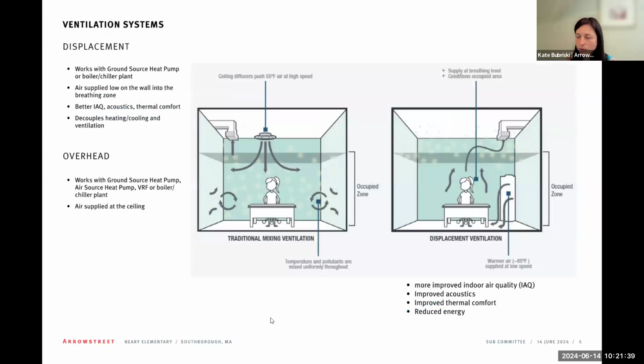And I don't know if everyone is familiar with displacement, so I'll just go over that a little bit. People are most probably familiar with traditional mixing ventilation systems where you're supplying overhead at the ceiling. You're also returning, usually on the other side of the room, at the ceiling level, and you're relying on higher velocity of air to come down and mix to provide the ventilation in the space.